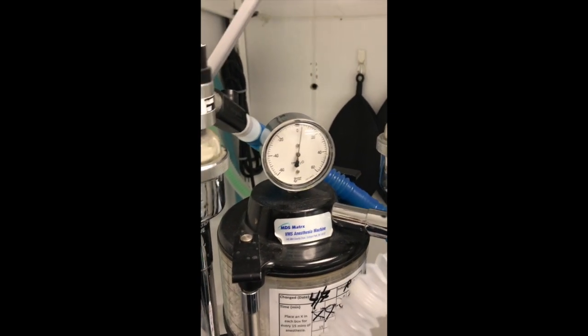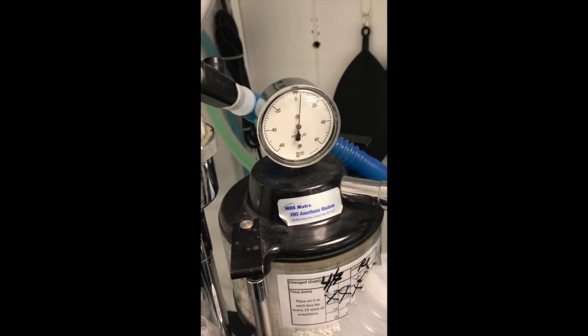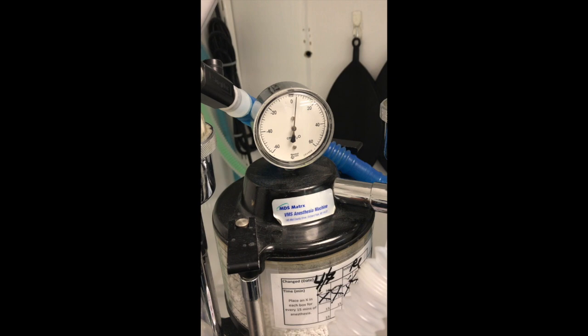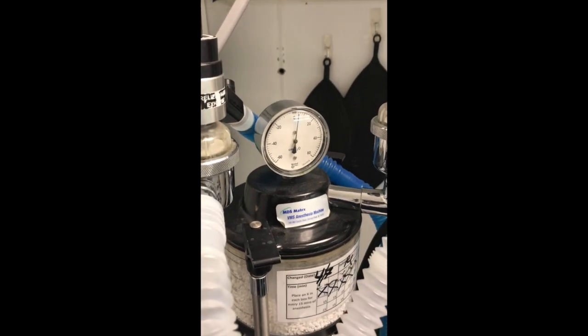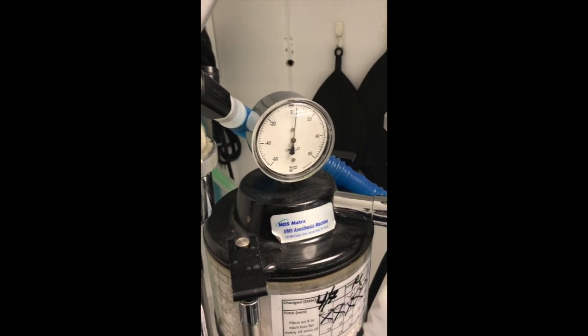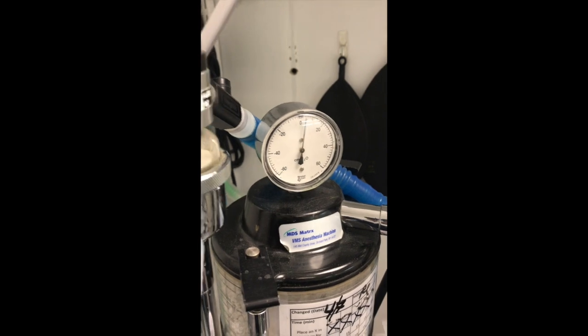the last thing I'll be talking about is our manometer here. The manometer is read in centimeters of water. It helps us measure the amount of pressure that we use during manual or partial ventilation. We have two different systems of our anesthetic machine, one called a rebreathing system and one called a non-rebreathing system. What I just went over is considered a rebreathing system. In our whole circulation of events, our patient will be rebreathing some of the exhaled gases that they have already inhaled and exhaled. They will be rebreathing these minus the carbon dioxide, because that could be very lethal.